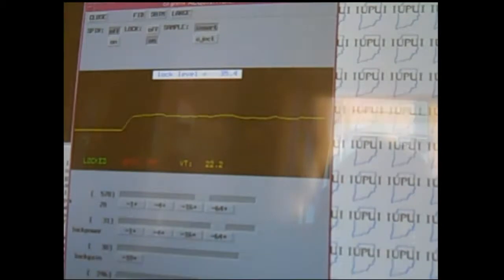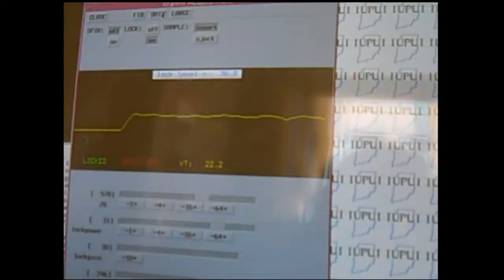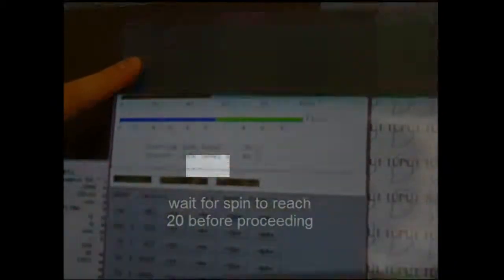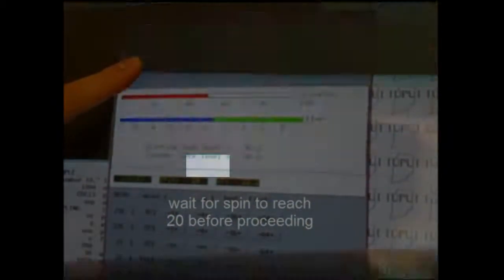At this point we'd move into the shim menu, which is up at the top. The shim menu will now launch you into some manual adjustments that you can do to the shim values. This helps maximize your lock signal. Before starting into the shim menu, make sure to click the spin toggle to on. By selecting that, the spinner is now spinning inside of the NMR instrument at 20 revolutions per second.